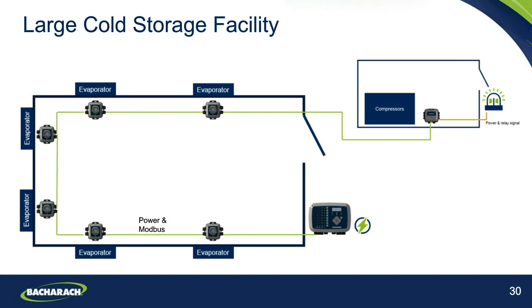Oftentimes it could be that we will see a higher level ammonia detector placed up closer to the ceiling where the gas is going to accumulate, but it wouldn't be uncommon to see the lower level sensors in the 30 ppm alarm region for toxic levels monitored actually lower down, because although the gas is going to rise, in terms of that human risk and human exposure, that is going to be where people are breathing. But of course, if you have multiple levels within a room with access platforms and such things, those need to be considered as well. So we do need to look at the physical properties of the gas.